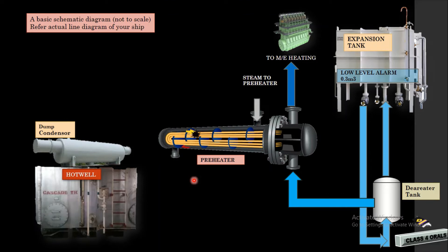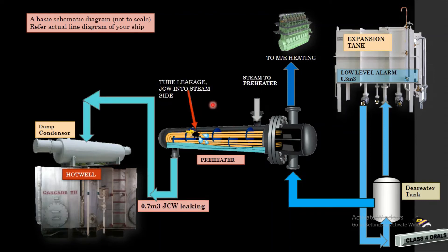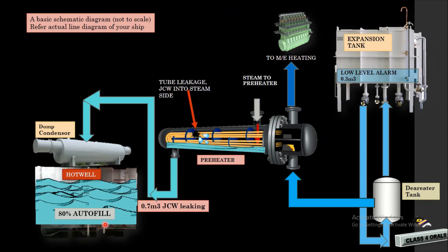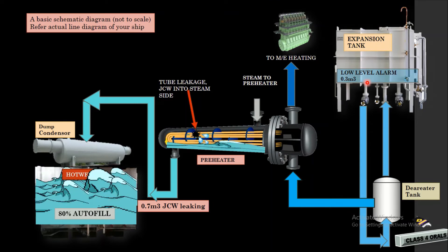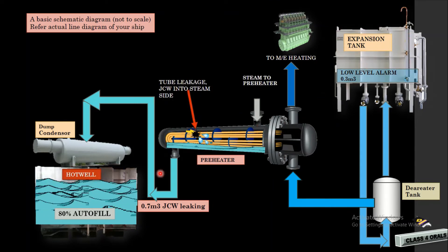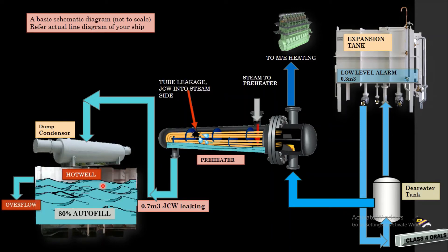But suppose there is a leakage or tube burst in the preheater. As we discussed earlier, the jacket cooling water will make its entry to the steam side and mix with the condensate. Then the condensate will go to the dump condenser, and from the dump condenser, the jacket cooling water will enter into the hot well. The hot well is already 80% filled, and the low level alarm of the expansion tank is at 0.3 cubic meters — meaning 0.7 cubic meters of jacket cooling water enters the 80% filled hot well, causing it to overflow.